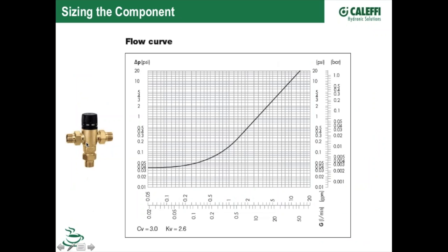And this is a thermostatic mixing valve, our 521 series. This valve could be used on domestic water, or it's commonly used as a mixing valve to mix down the lower temperature off a high temperature boiler. This valve has a flow rate Cv factor of 3.0, so that's 3 gallons a minute that can move through this valve with a 1 pound pressure drop.